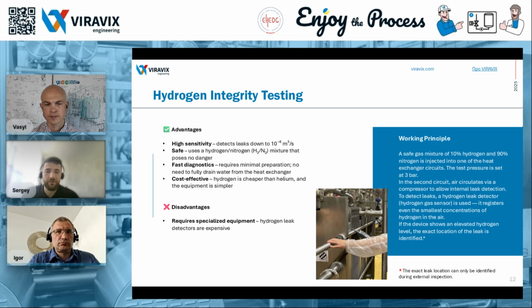It doesn't require lengthy preparation, and there's no need to completely drain water from the heat exchanger before testing. And it's also cost-effective. Hydrogen is cheaper than helium, especially when compared to the helium method. Plus, the equipment used is simpler and less expensive. As for the disadvantages, specialized equipment is required, namely a hydrogen detector, which is quite expensive. Finally, it's not suitable for heavily contaminated heat exchangers, as the presence of foreign gases may lead to false readings.